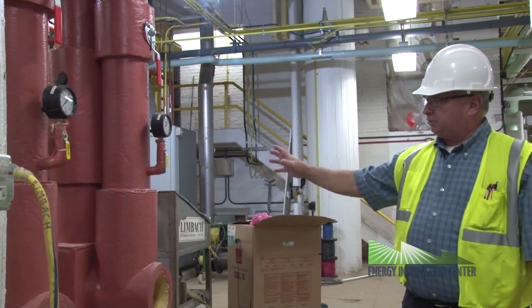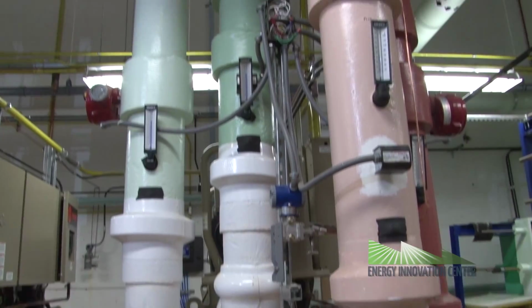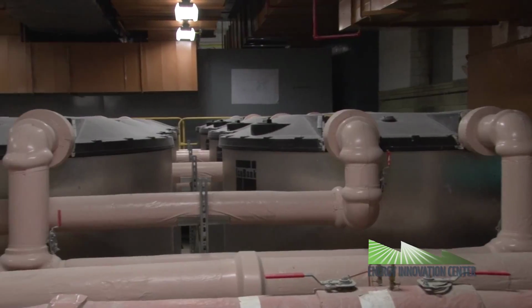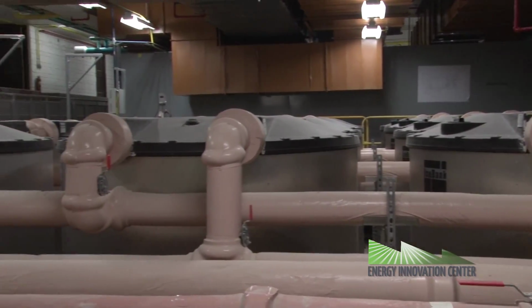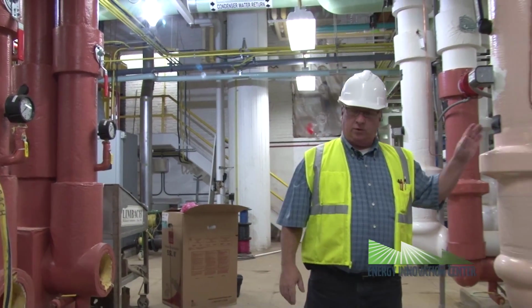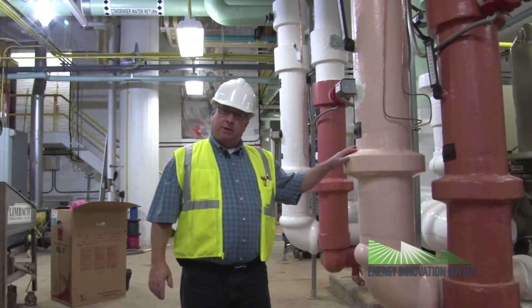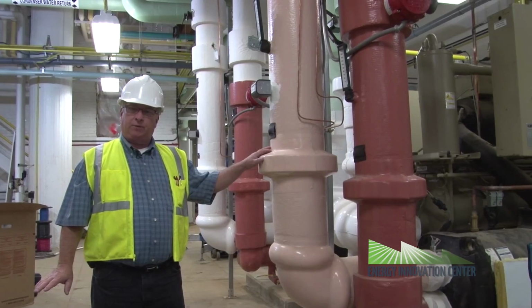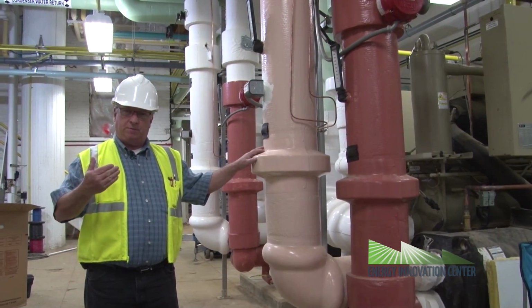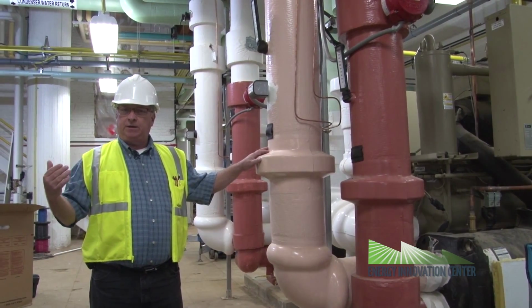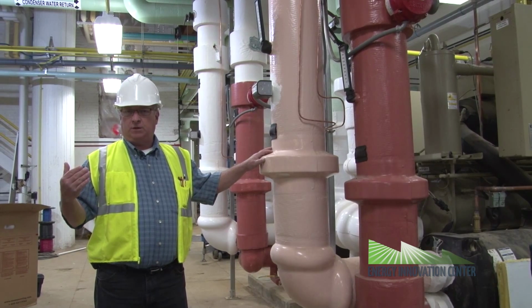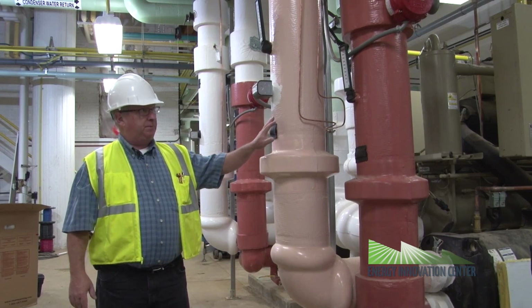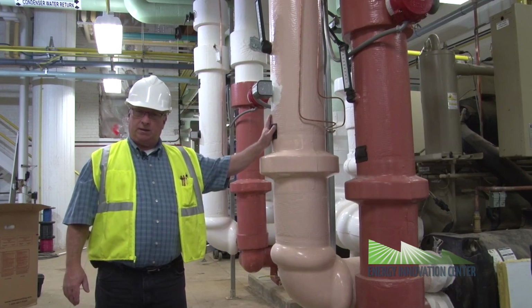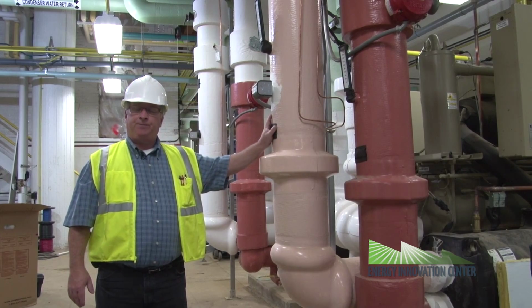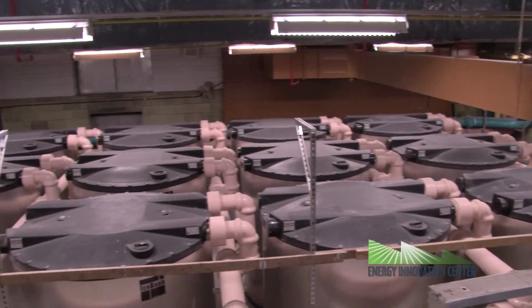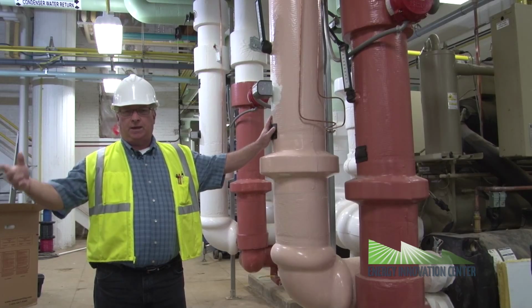These pumps strictly pump between these chillers and our ice storage tanks in the other room. And as we're pumping through here, during normal operation, this chiller is operating at a 41-degree operation. That's when we're bypassing, we're not making ice. But in the evening, when the electrical rates are lower, we're lowering the temperature of our chill water in our glycol down to 26 degrees. We send it to our ice farm, and we make ice all night long.